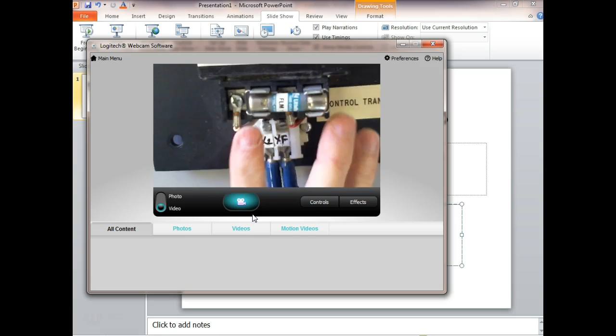Everybody okay there? So the X's are the low side, the H's are the high side. Now here all our controls are rated at 120. We don't have 240, but let's use that as an example. We're getting 240 out of our disconnect—actually 208, but we'll talk about that later. So what do we want our transformer to do? We want it to step down.